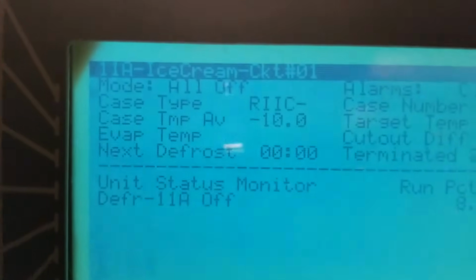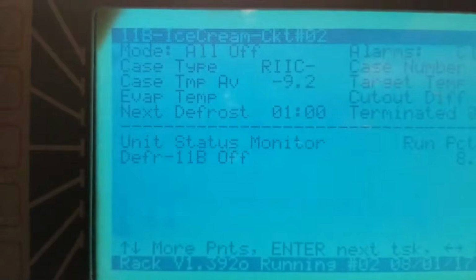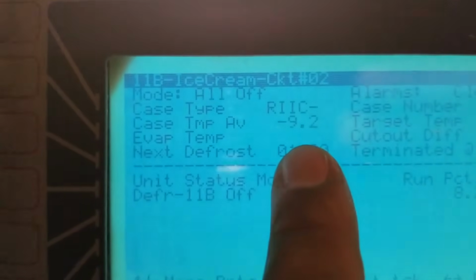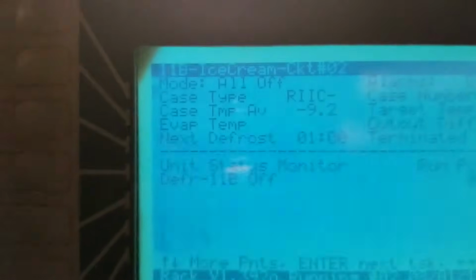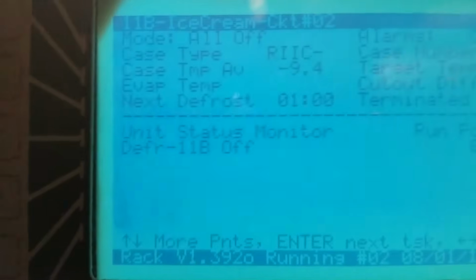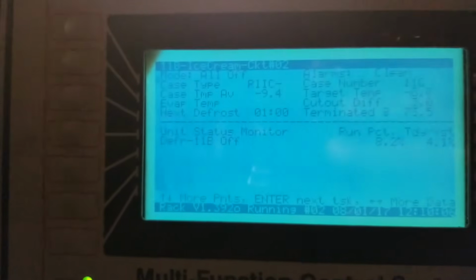So if I look at this temperature, -9, and then I go down to my case, that does read -9. So it's reading correctly now, and I have another one that I had to calibrate as well. So let me back out of here. We go to B, and I had to do the same thing here. Right here it was reading like -1 degree. So I had to calibrate this as well to make sure my temperature sensors match my actual digital temperature on my Fluke meter downstairs at the case. Now that I've got everything calibrated on my temperature sensors, I will go down to the case and you'll see that the temperature is actually cooling down into the minuses. Alright guys, hopefully I didn't lose you too much on that floating suction. Alright, let's go downstairs and check out the temp.